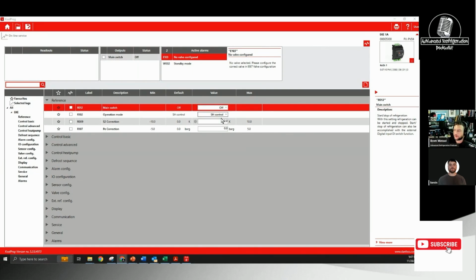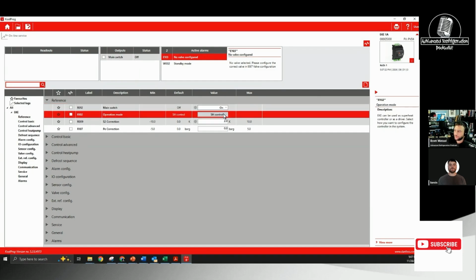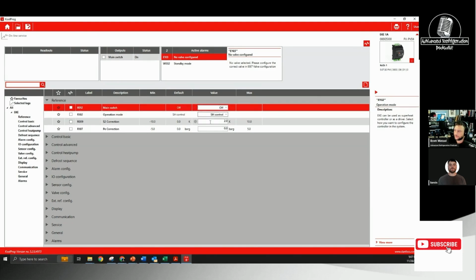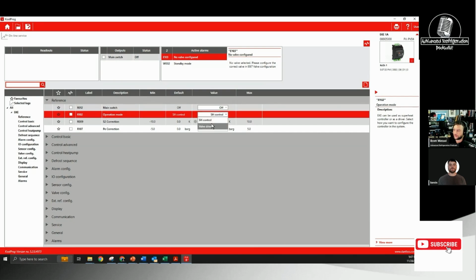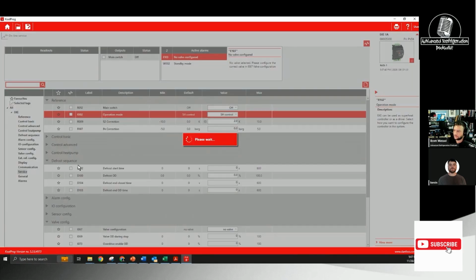So you can see up on the screen, right now it has that main switch, just like the pack controller, where it's either on or off. If you have it in the on position, I can't change any of the parameters. In order to actually change any of the parameters, just like the pack controller, you have to have it in the off position. Now I can change it to either superheat control or I can change it to valve driver.